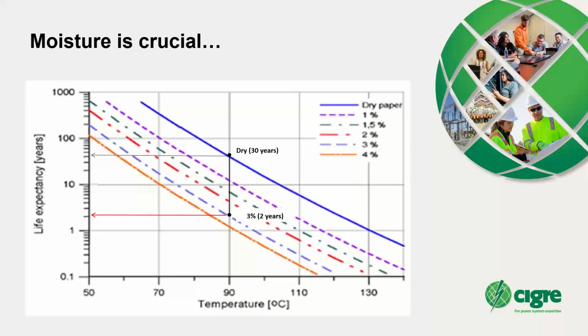As both Dan and Ivanka said, moisture is really crucial for transformers. In this slide, I'm highlighting that when the moisture in the paper goes up - let's say we have a dry transformer, less than 1%, operating at a hotspot of around 90 degrees, we expect it to last 30 years. But if the moisture goes up, the expected life of the paper goes down. That is the reason why moisture is crucial.